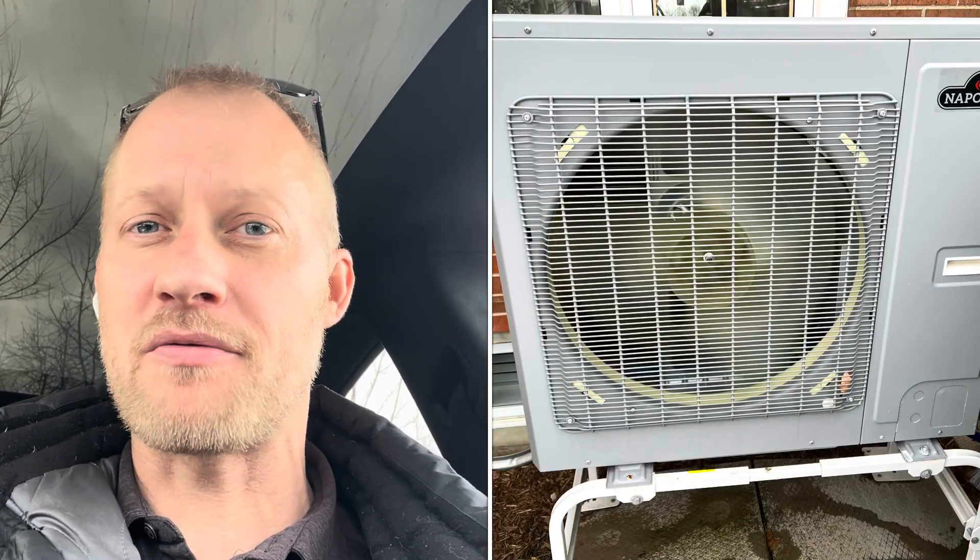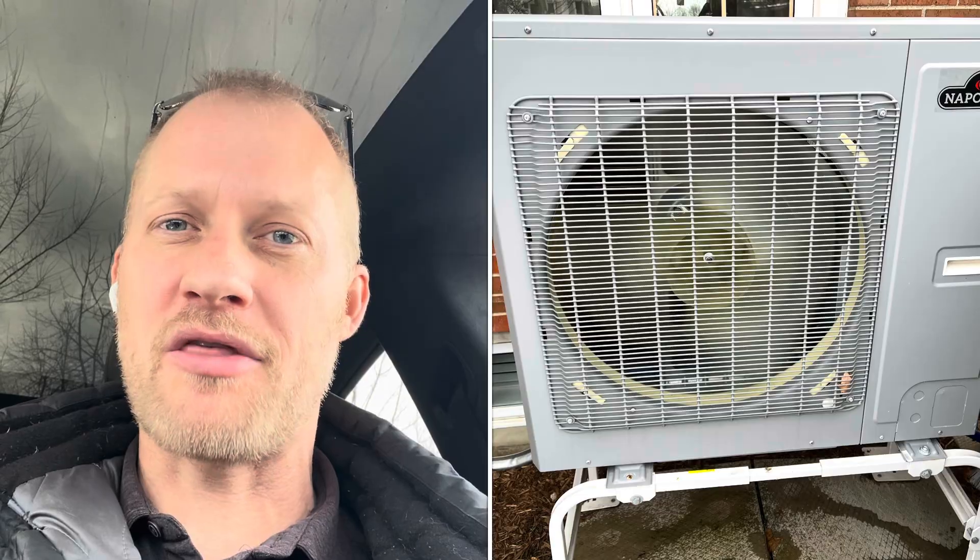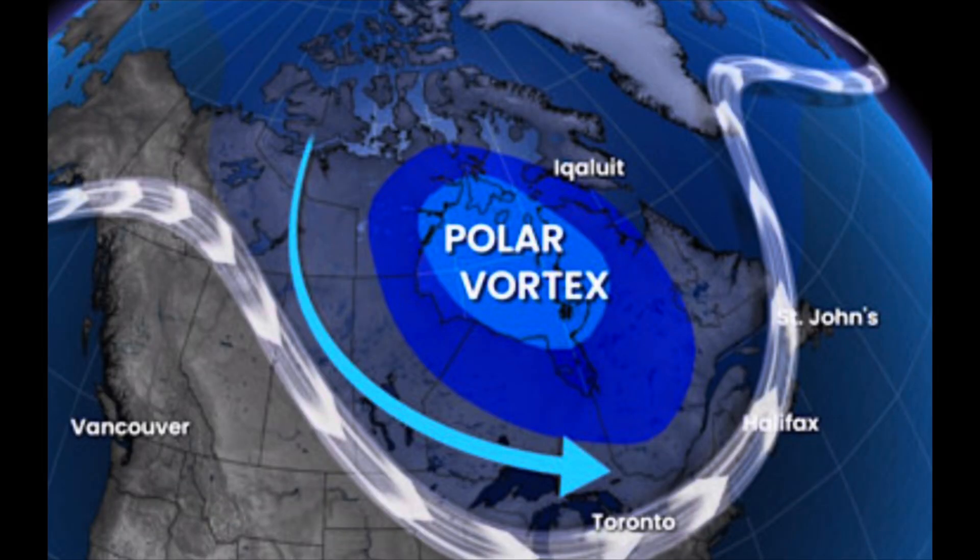Thanks for checking in. I've owned my heat pump in Canada for two and a half winters now — I'm halfway through my third winter. We just got through one of those polar vortex cold air masses where everything is insanely cold. It was about three nights getting down to minus one Fahrenheit, which is close to minus 19 Celsius. I want to share my data over the last few years: what does it cost to run this heat pump, how much energy does it use, and is it worth it?